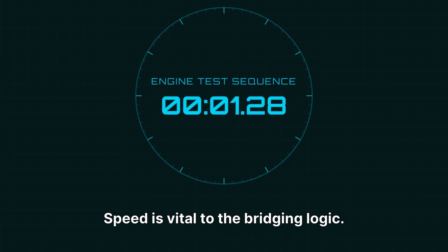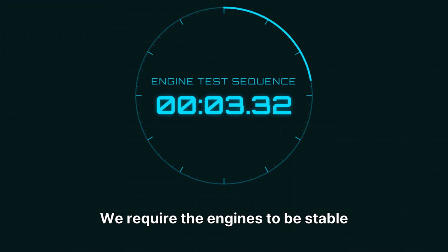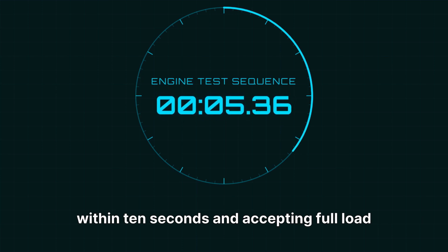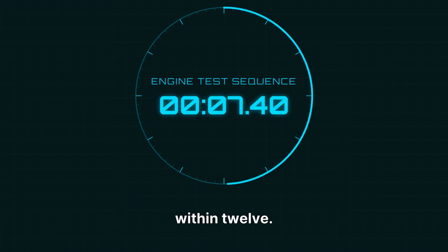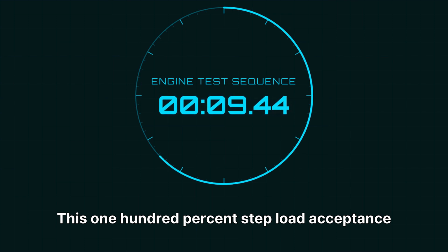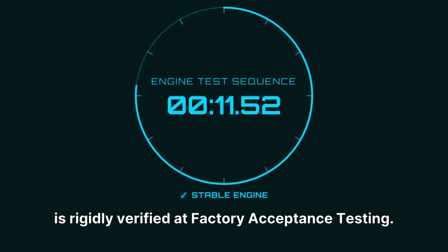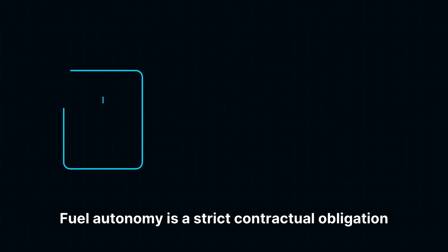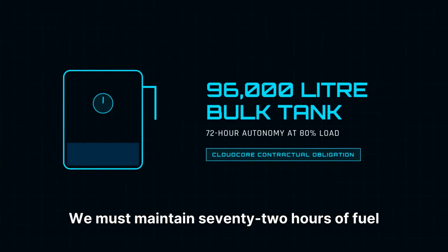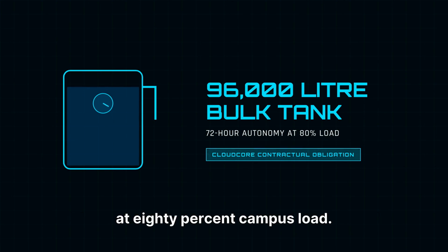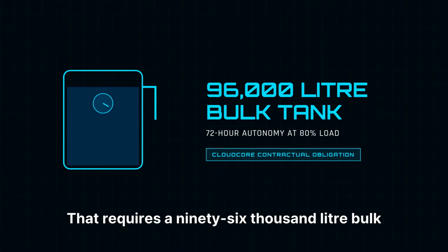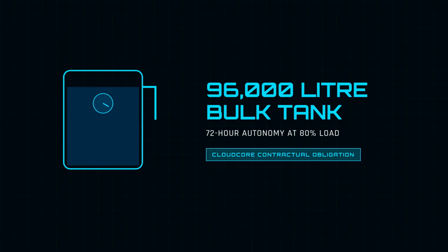Speed is vital to the bridging logic. We require the engines to be stable within 10 seconds and accepting full load within 12. This 100% step load acceptance is rigidly verified at factory acceptance testing. Fuel autonomy is a strict contractual obligation to CloudCore. We must maintain 72 hours of fuel at 80% campus load. That requires a 96,000-liter bulk storage system.